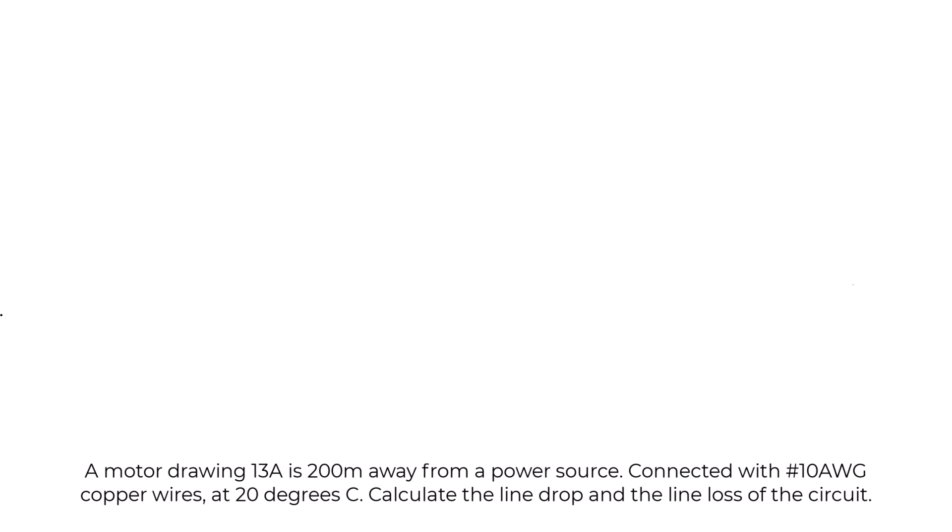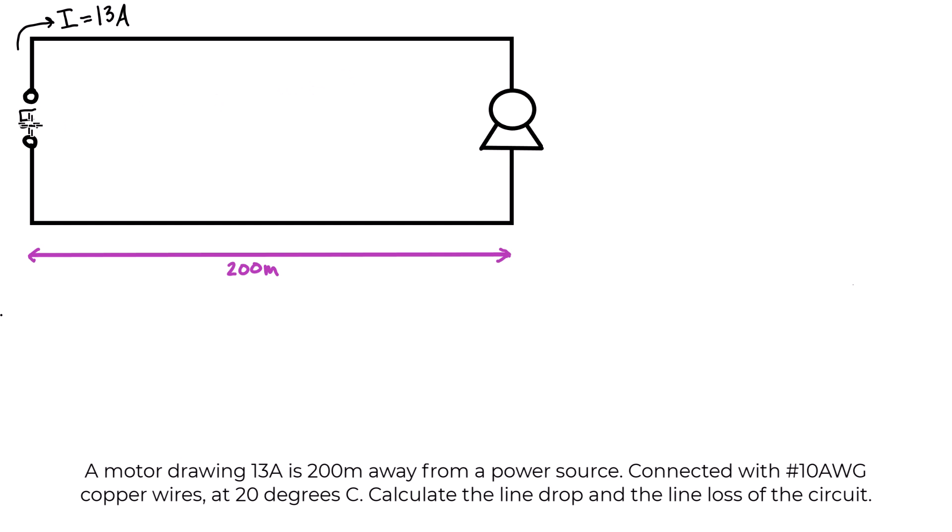For this problem, the circuit looks basically like this: we have our source of power, then 13 amps of current flowing through our motor 200 meters away. Often this is a trick question because we have a wire here that's 200 meters long and a wire here that's 200 meters long, so we have 400 meters of wire total.